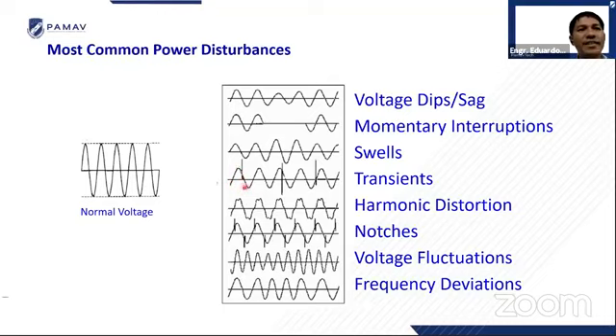See, if we have here one cycle at 60 hertz, the 60 hertz is 16.66 milliseconds. So if you look at the transient, it's almost nothing, okay? So sometimes we don't know that a transient happened unless you have a recorder that can record transients. But for starting a motor, we call it a transient because there is exciting current. So if you start big motors, suddenly your current will go up, but for a certain time only. But we need that kind of starting because we will set our protective relays for what we call exciting current or inrush current.